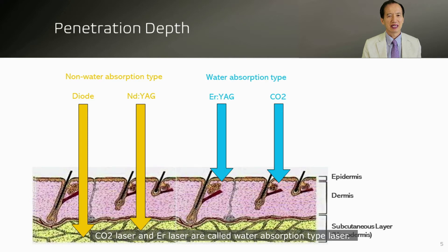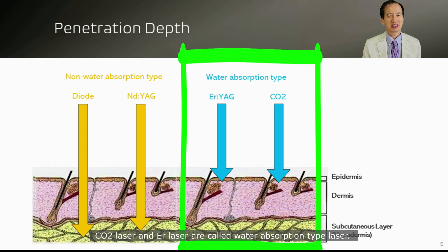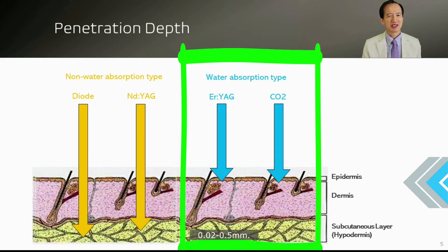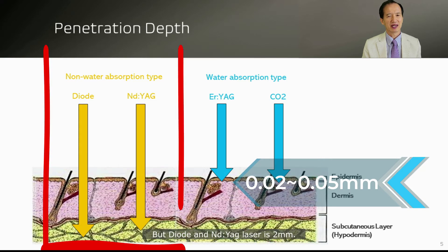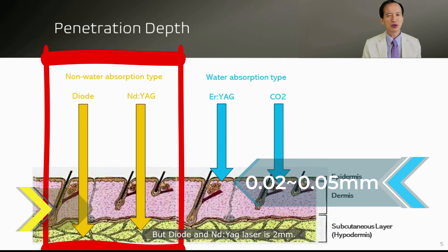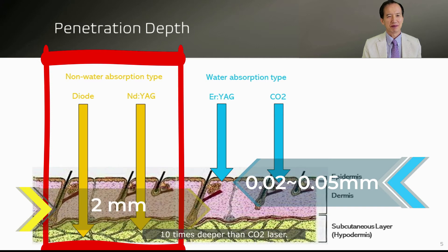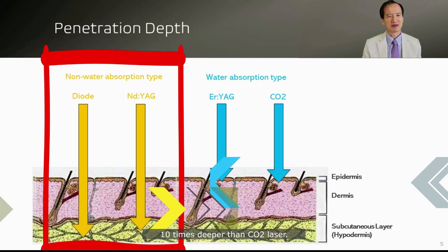CO2 laser and ER laser are called water absorption type lasers. The penetration depth is very shallow: 0.02 to 0.5 mm. But diode and Nd:YAG laser penetrate 2 mm — 10 times deeper than CO2 laser.